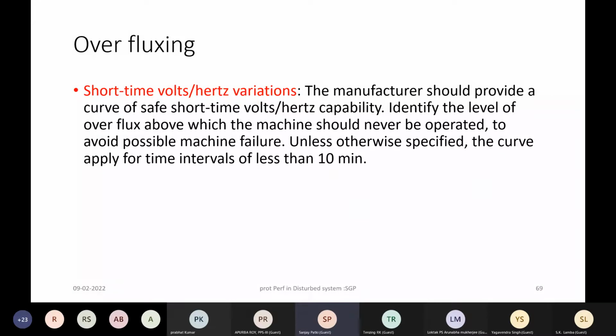Next protection which again gets affected during grid disturbance is overfluxing protection. This overfluxing protection either can be during the system disturbance, unstable operation, or after isolation when the region gets isolated. Again, depending on whether you are importing the reactive power from other region or you are exporting. If you are exporting reactive power and isolation takes place, then you will have excess reactive power resulting into over voltage, and overfluxing condition can happen.